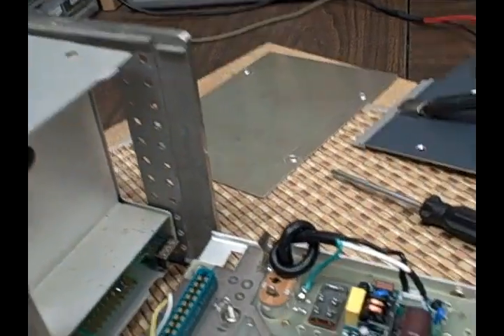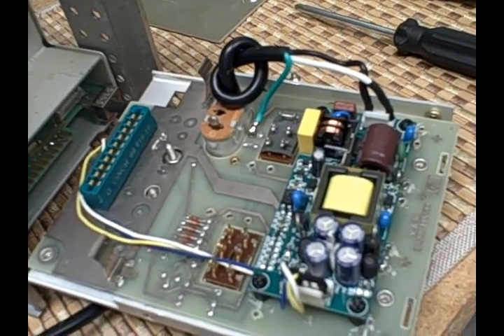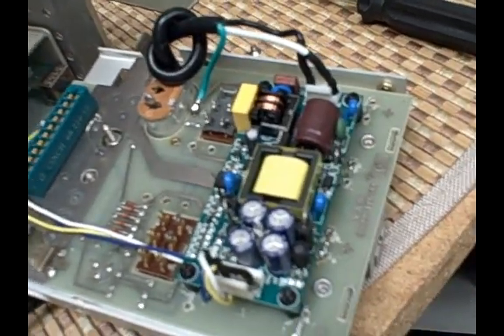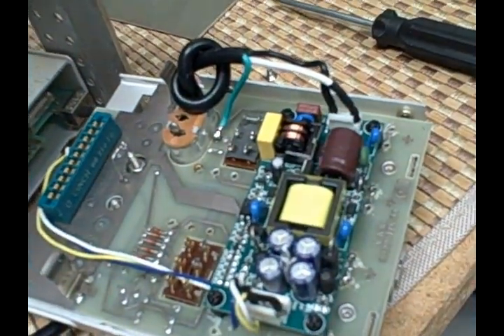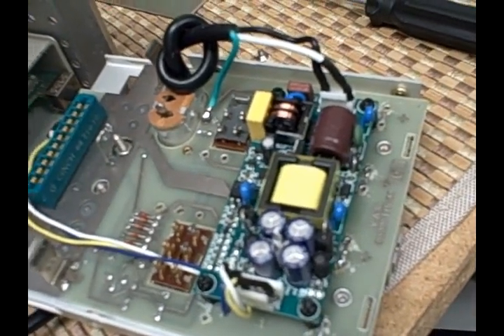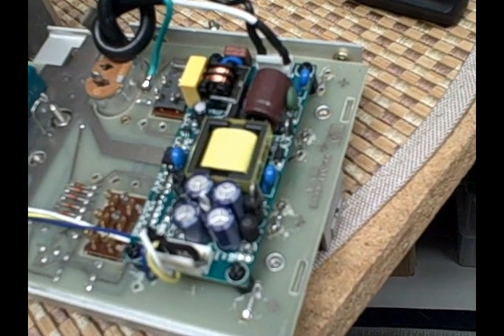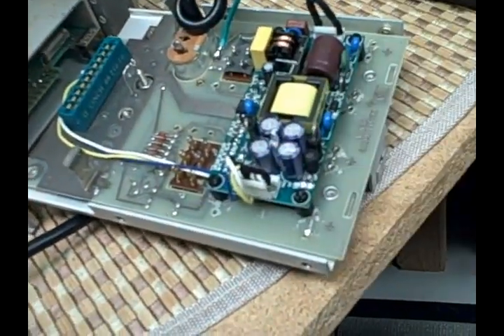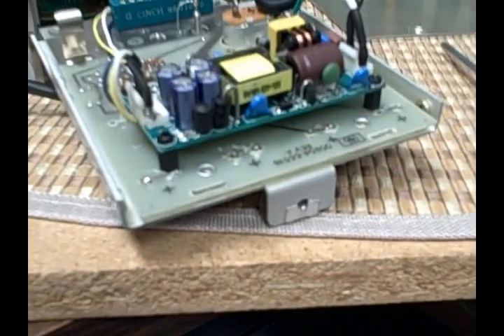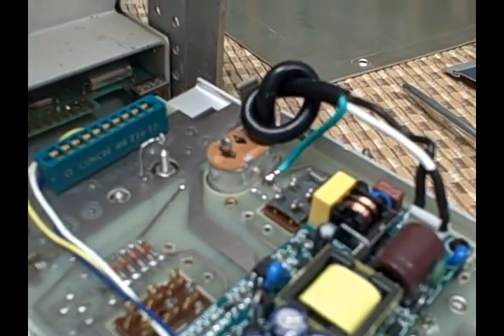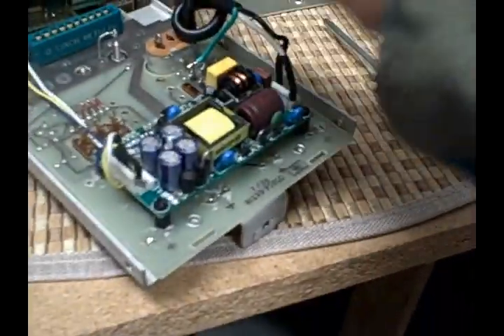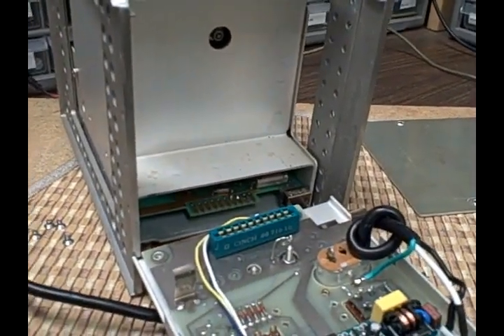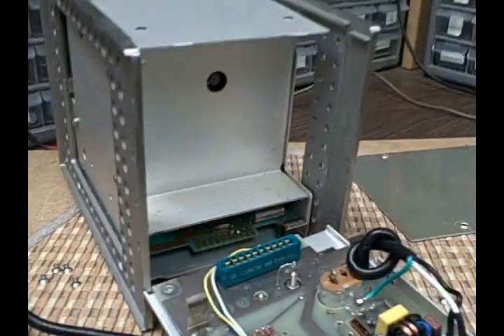All right, I've disassembled the case on this HP 204C and showing you the power supply that's been installed on the power supply board. At one time this was for rechargeable batteries and they had gone bad and just damaged the board and was basically unrepairable in my opinion. So I put this modern plus or minus 12 volt power supply in here. Did a good job, decent job of it, nice plastic standoffs and plenty of space. Replaced the old-fashioned three-prong cord which is very difficult to get and expensive with a standard cord. And that's basically what I wanted to show you here. So I'm going to go ahead and put it back together and we'll test her out.